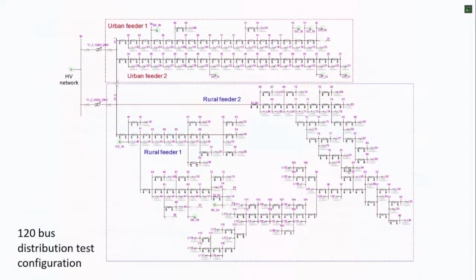We considered different scenarios, but I will show results where the production here is quite heavy, so there are several hours in which the flow, instead of going from the high voltage network to the distribution network, goes back from the distribution network to the high voltage network. The power is positive when the network consumes power from the high voltage network, and negative when there is this counter flow.